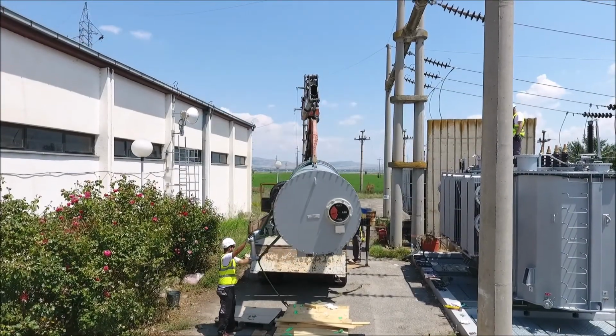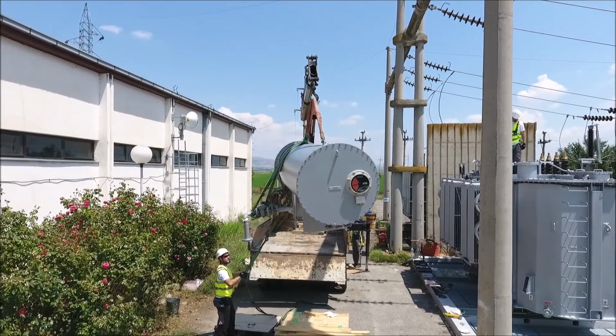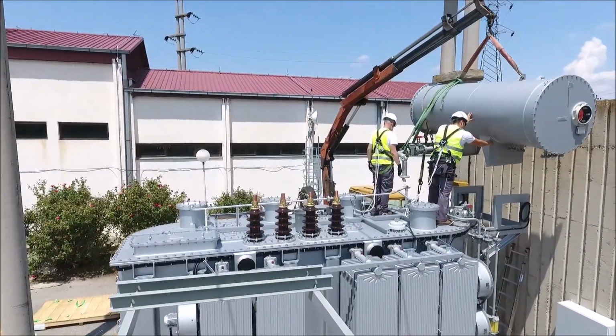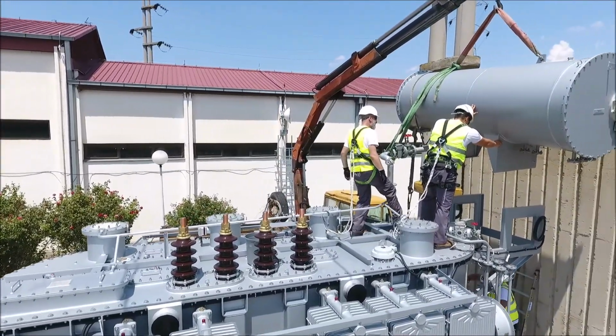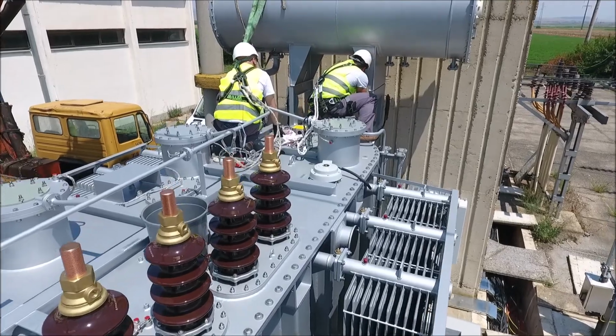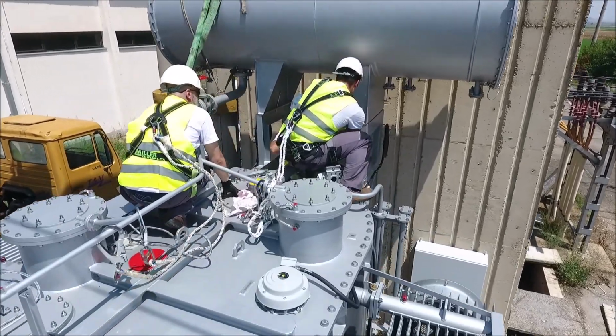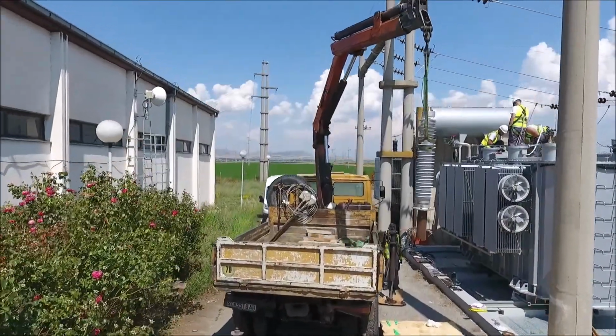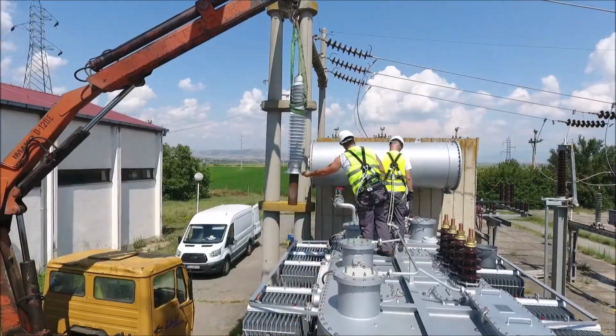Every additional part has a strict order of mounting. Some of the equipment that needs to be mounted are the wheels of the transformer, cooling radiators, cooling fans and pumps, the conservator and the pipework. The bushings are the most delicate equipment and they take the longest time for mounting.